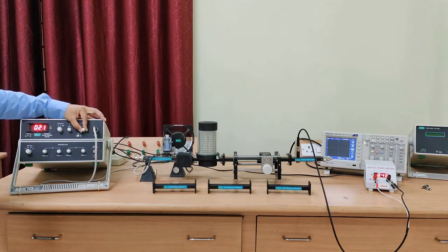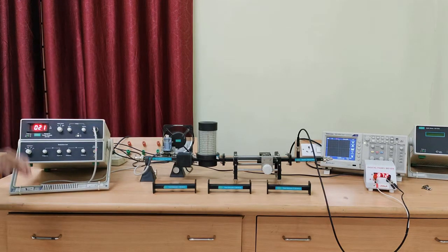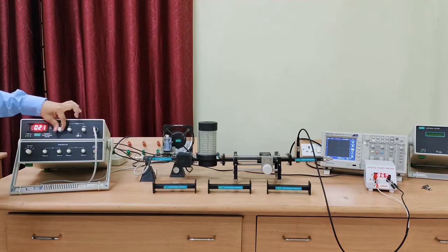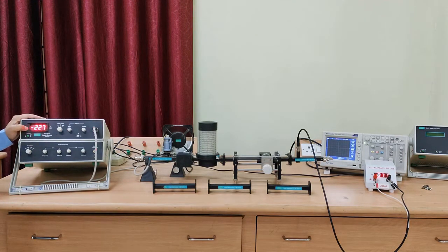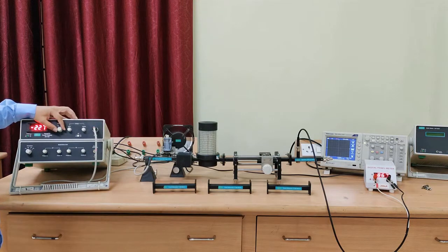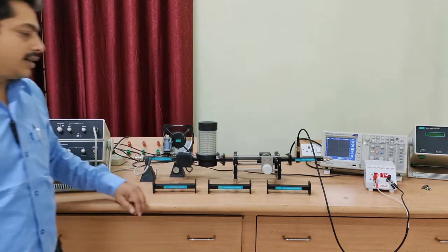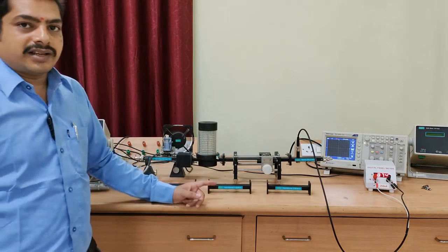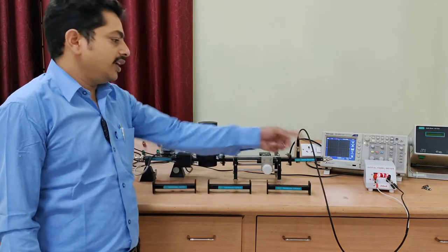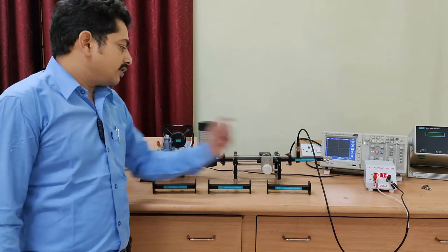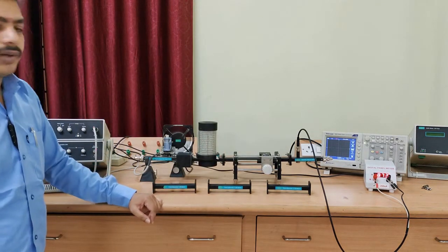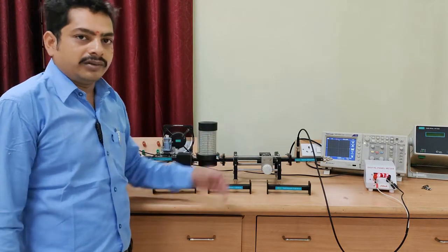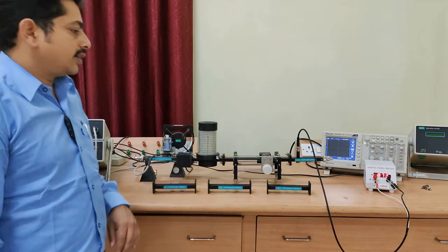By varying regulated voltage, we have to check. At 227, I am getting 860 microamps of current. Now it is the initial current to the test bench. So it is Imax. We have to write down these values.